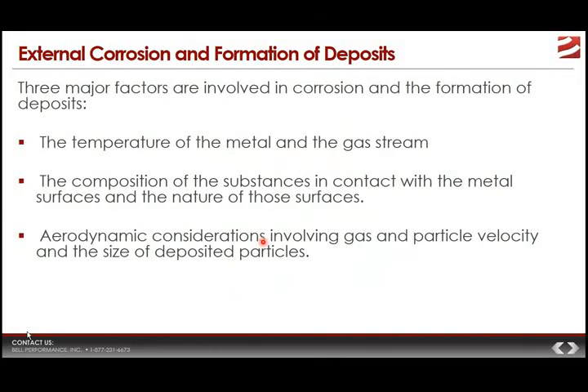There are three primary contributors to the formation of boiler deposits and corresponding corrosion issues. Like so many things in combustion chemistry, temperature has a significant influence. The composition of the substances in contact with metal surfaces plays a key role, because composition determines what deposits are made of, and the physical characteristics of those deposits directly impacts the problems they may contribute to. Aerodynamic considerations also come into play, influencing how particles in the combustion gas stream attach to metal surfaces in the boiler.